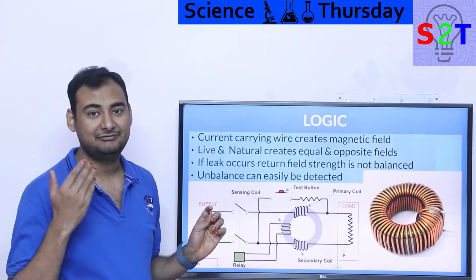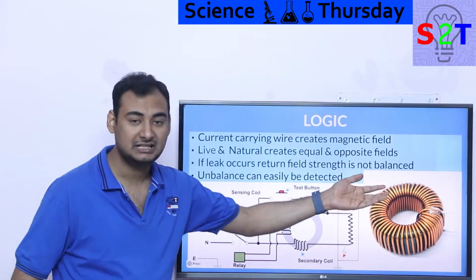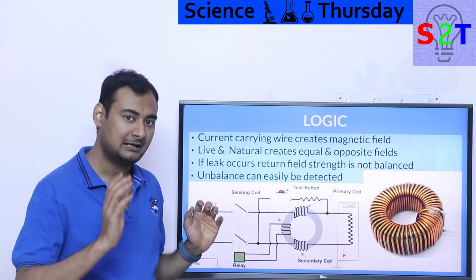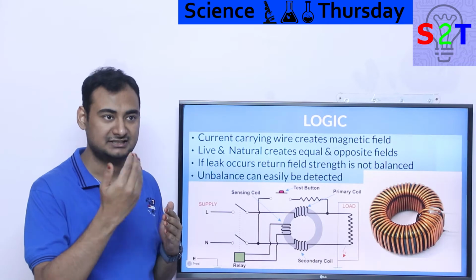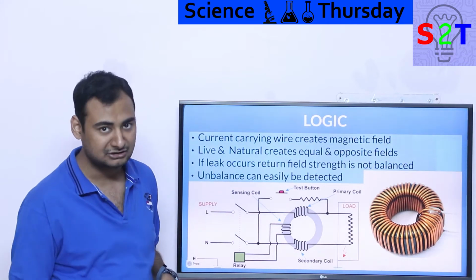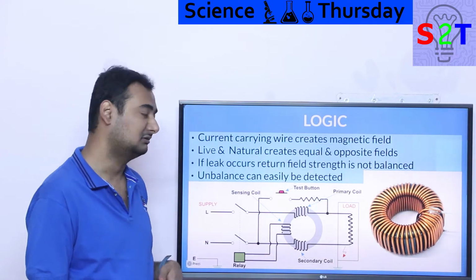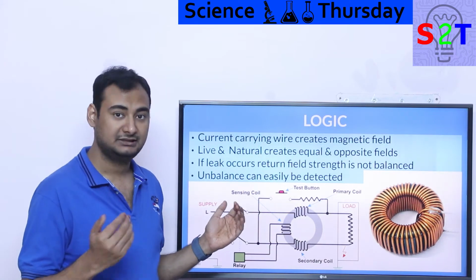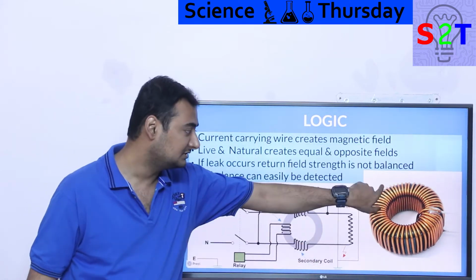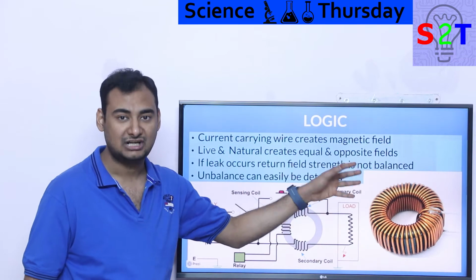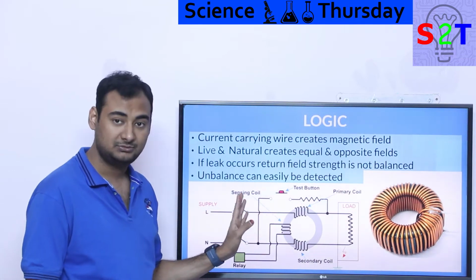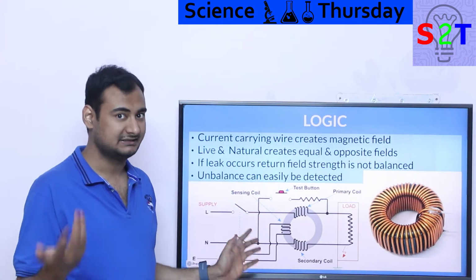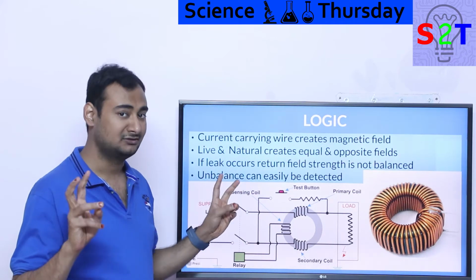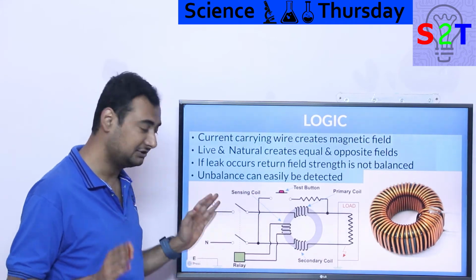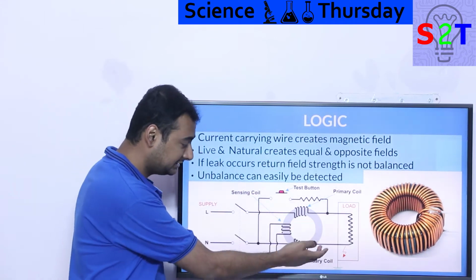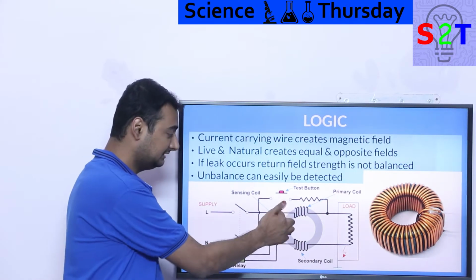Now, what happens if it's unbalanced? That's the tricky part. The moment, let's say 100 ampere was sent, and not 100 was returned, let's say 90 was returned because 10 ampere went through some ground leakage or some person, then you have an unbalance. In that unbalance, this toroid basically will become charged. Basically, there will be a third coil that could detect, hey, it's in the quote unquote on state. It should not be in on state, it always should be in off state. If current went in, current went out, everything is the same, this will be in off state.